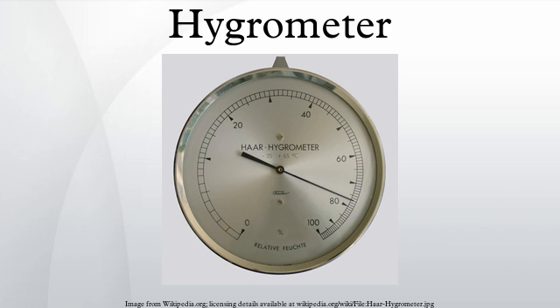Saturated salt calibration. Various researchers have investigated the use of saturated salt solutions for calibrating hygrometers. Slushy mixtures of certain pure salts and distilled water have the property that they maintain an approximately constant humidity in a closed container. A saturated table salt bath will eventually give a reading of approximately 75%. Other salts have other equilibrium humidity levels: lithium chloride 11%, magnesium chloride 33%, potassium carbonate 43%, potassium sulfate 97%.